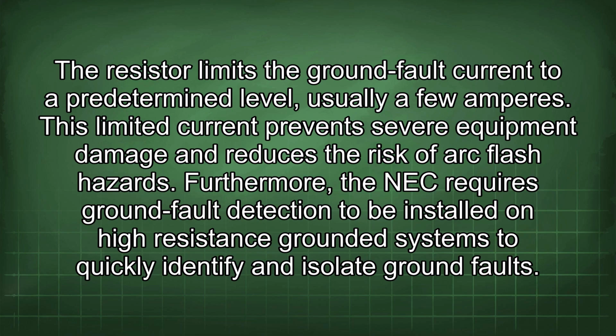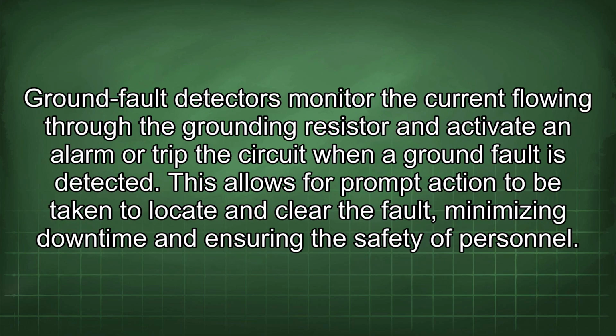Furthermore, the NEC requires ground fault detection to be installed on high-resistance grounded systems to quickly identify and isolate ground faults. Ground fault detectors monitor the current flowing through the grounding resistor and activate an alarm or trip the circuit when a ground fault is detected.